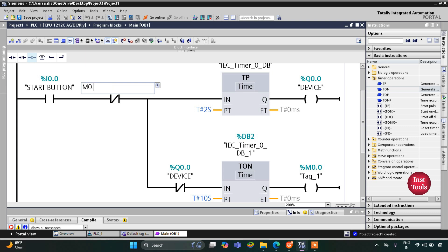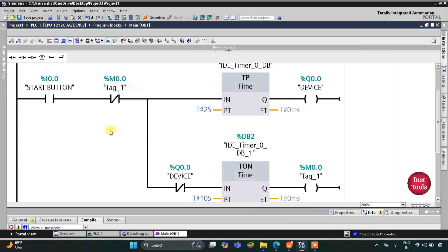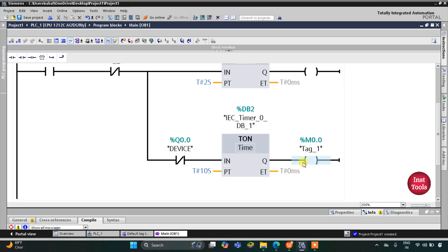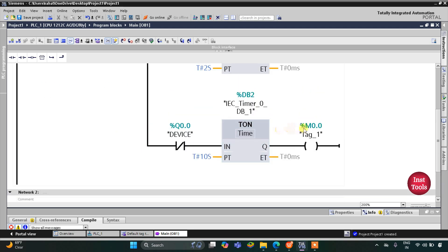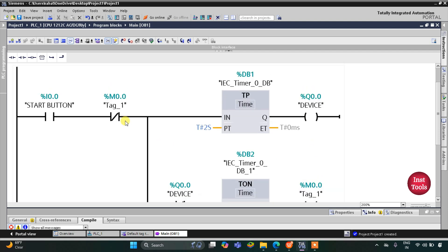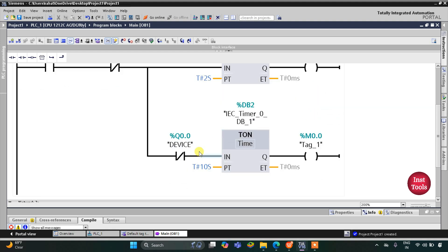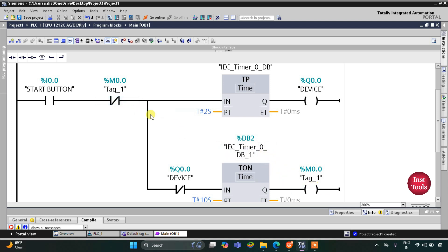When M0.0 turns on, we use it as a normally closed contact in the main rung. So when the device is off, after 10 seconds M0.0 goes true, current stops flowing through the NC contact, M0.0 resets, and once M0.0 resets current flows again — the TP timer restarts and the device turns on for two seconds. After two seconds the device turns off, the TON starts, waits 10 seconds, M0.0 goes true and off again, and the device turns back on — repeating the cycle continuously.